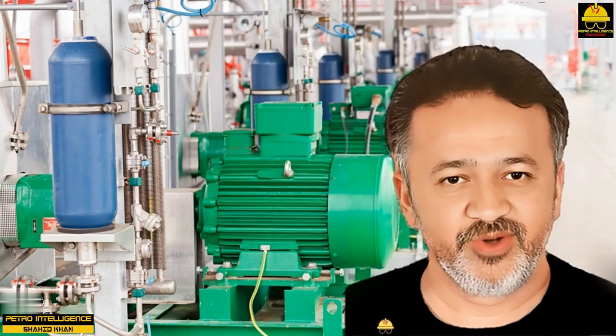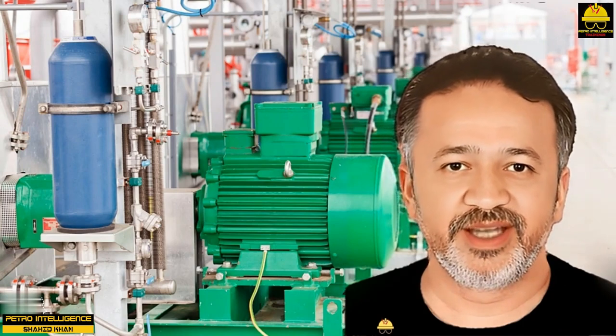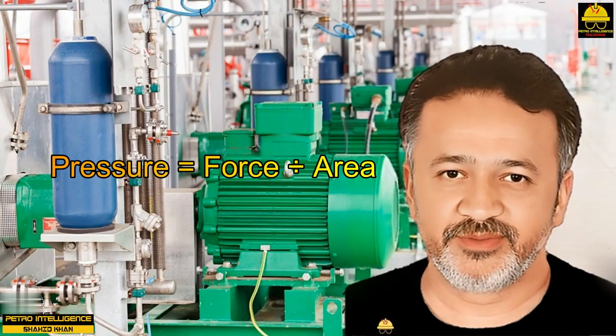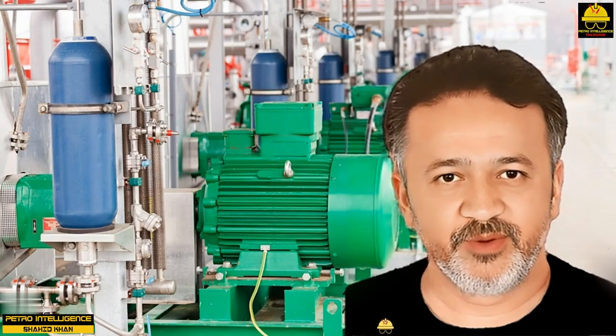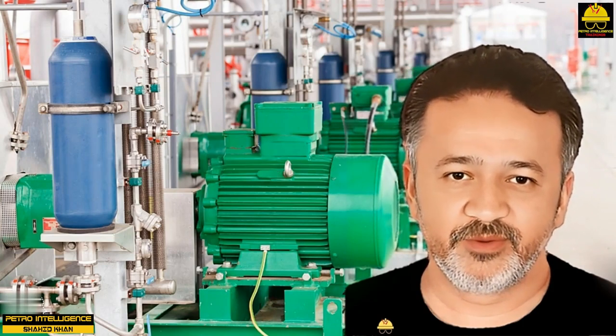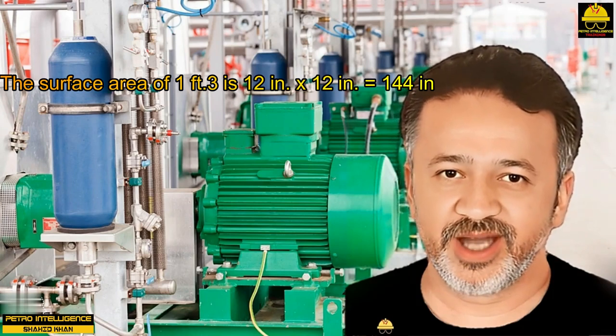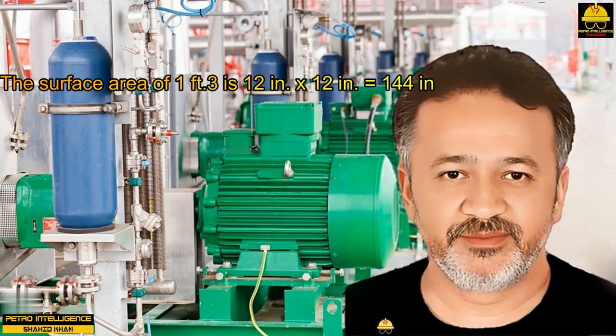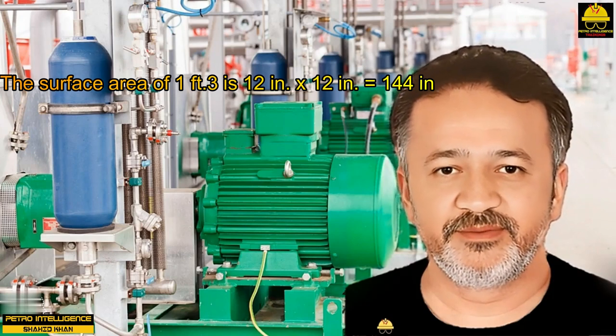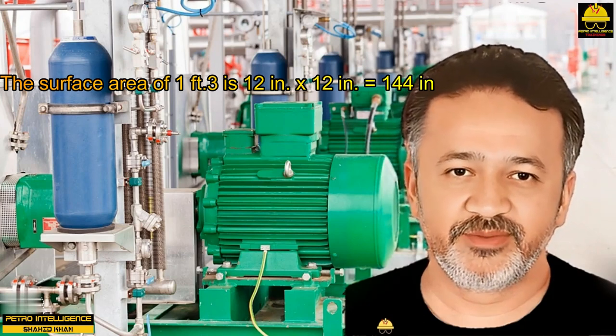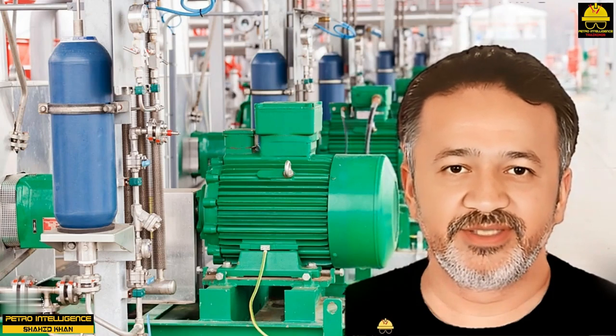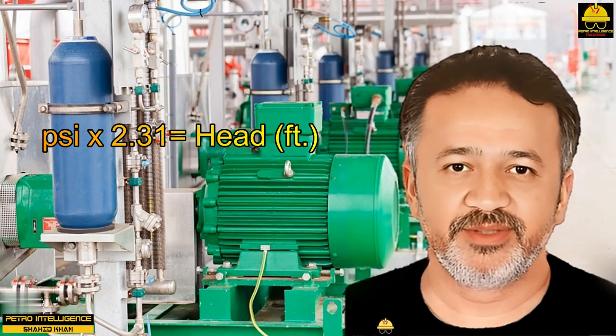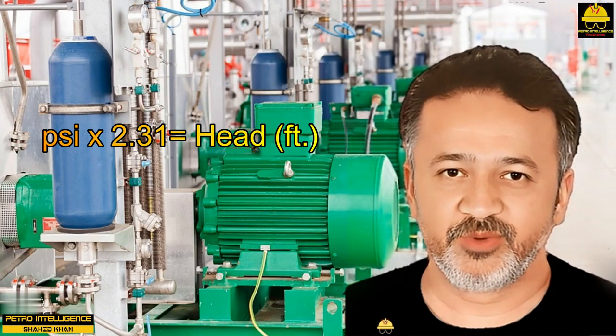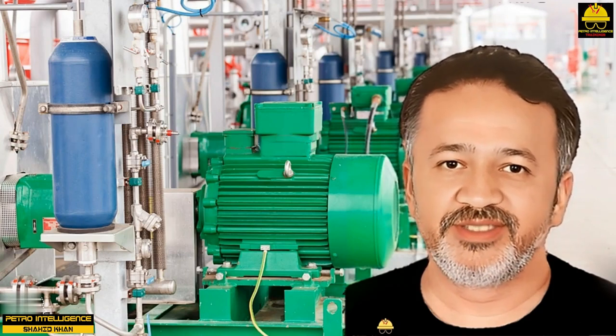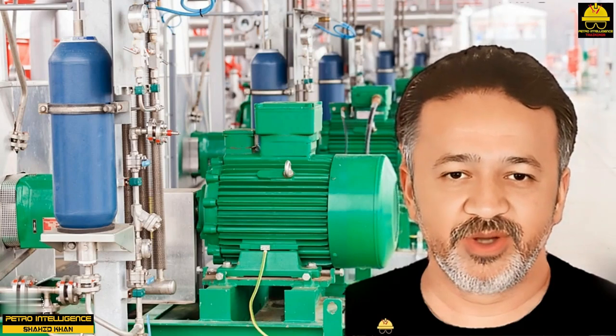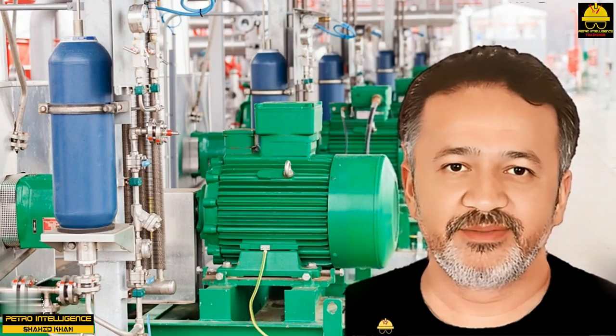To calculate the pressure produced by 1 cubic foot of water, we need to use the equation pressure equals force divided by area. 1 cubic foot of water weighs 62.4 pounds. The surface area of 1 cubic foot is 12 inches times 12 inches, equals 144 square inches. For water, 62.4 divided by 144 is equal to 0.433 psi. For each additional foot of water, an additional 0.433 psi can be added.